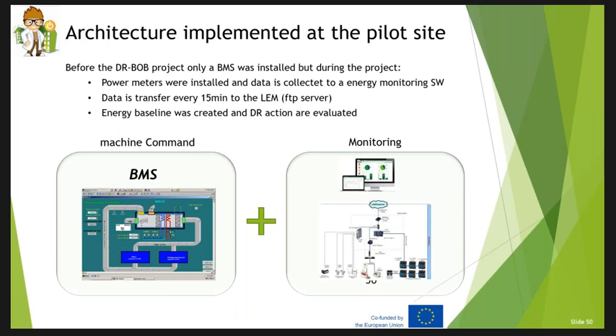So what we did during the project was installing several power meters for electric energy, gas, and heat and cooling capacity, and a software that was able to collect, record, and display all the data for the definition, for example, of a baseline. The software also displays instant values and records values every 15 minutes that, for the project, are sent to the LEM through an FTP server. And as I said, thanks to the data, we can define our baseline and monitor the effectiveness of the demand response events.